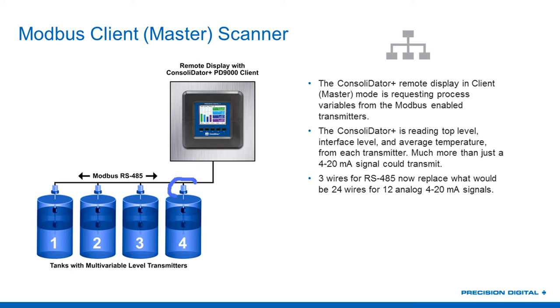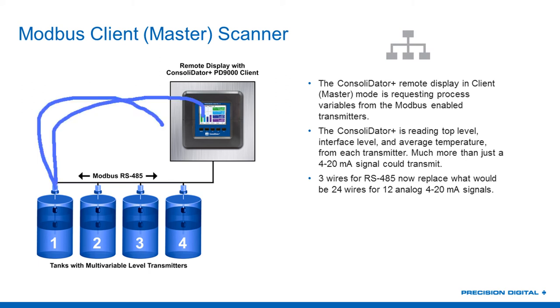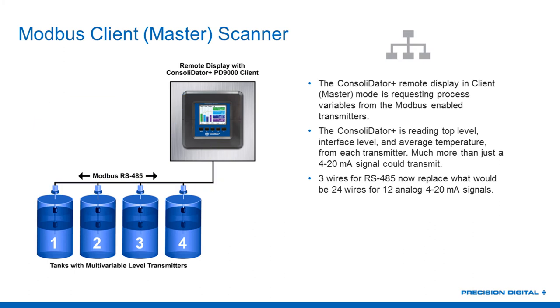In this example, each one of these Modbus multivariable level transmitters is displaying top level, interface level, and average temperature along the probe in four different tanks — a total of 12 process variables. If I were going to do that with 4-to-20 milliamp, I'd have to run 24 wires back to the Consolidator. A much more convenient way is to just run one RS-485 bus line — three-wire 485 running out to all of these transmitters, keeping everything in parallel. The Consolidator Plus is then set up to be the client or master.